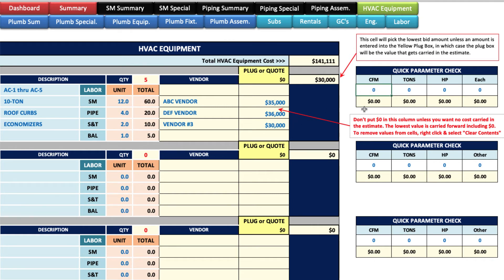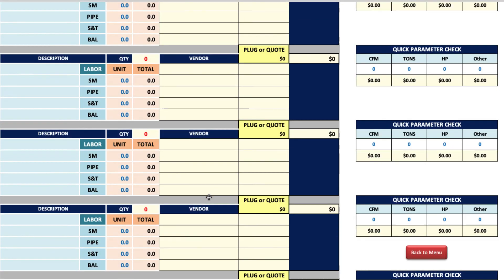Over here you can check your parameters. Those 10-ton units — five of them — let's say that's 20,000 CFM. Right away it tells you you're paying $1.50 per CFM for those units. And then for tons, five times 10 is 50 tons, so it tells you you're paying $600 a ton. If you want to see cost per unit — they bid a lump sum of $30,000 for five units — you're getting charged $6,000 a unit, $600 a ton, and $1.50 per CFM. This is a quick parameter check available on each equipment sheet.